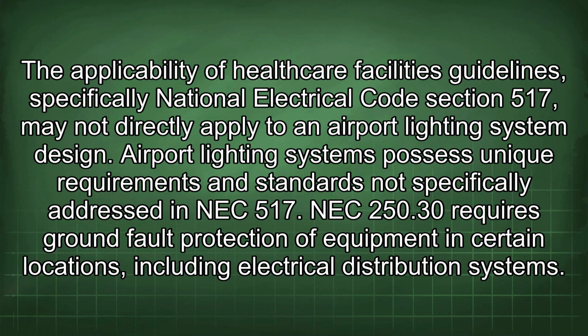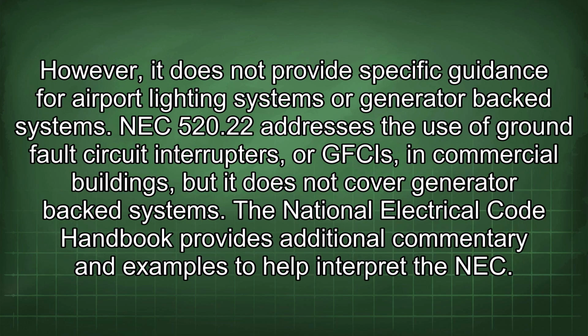The applicability of healthcare facilities guidelines, specifically National Electrical Code Section 517, may not directly apply to an airport lighting system design. Airport lighting systems possess unique requirements and standards not specifically addressed in NEC 517. NEC 250.30 requires ground fault protection of equipment in certain locations, including electrical distribution systems. However, it does not provide specific guidance for airport lighting systems or generator-backed systems.